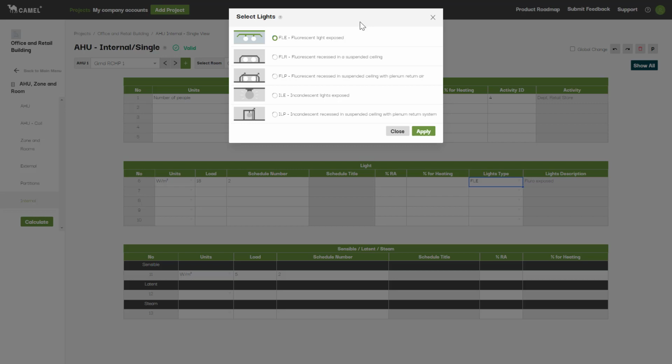This is used in determining the storage load factors for the lights and follows the methodology set out in the ACADS-BSG DA9 3rd edition. Note that these options are quite old and that there is an obvious lack of an LED option. Most of the time, your selection here won't have a significant impact on your results, particularly if you aren't using a schedule and are running your lights at 100% throughout the day. We will be updating this section once the new edition of the DA9 is released, which is currently in the works.